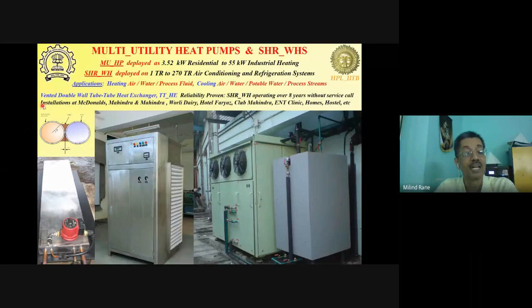Then for places where you need hot water and you have existing air conditioners deployed, we have developed what we call a superheat recovery water heater. And this superheat recovery water heater basically gets connected between the compressor and the condenser. So the superheated vapor going from the compressor outlet to the condenser is routed through this heat exchanger, and hot water is generated using this heat, which is otherwise wasted.